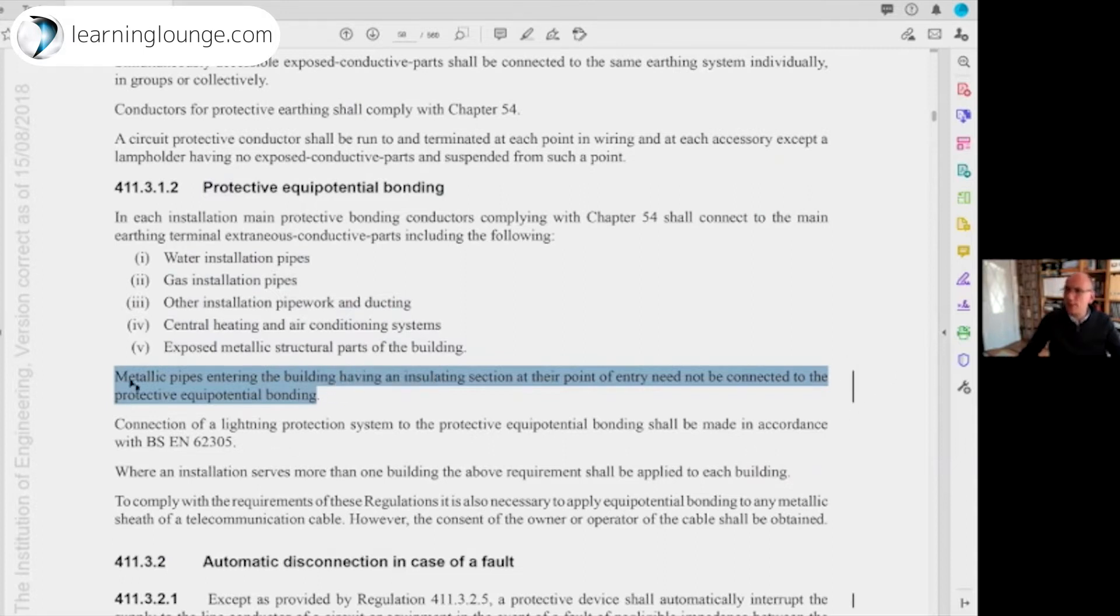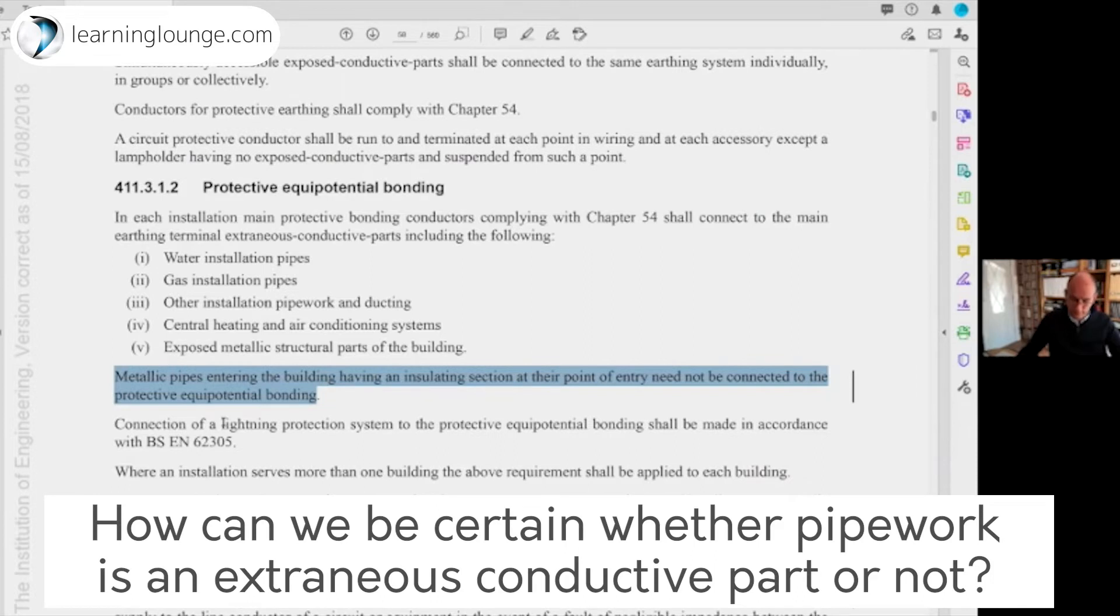What it states is that metallic pipes entering the building having an insulating section at their point of entry need not be connected to the protective bonding. It's not quite as clear as it could be. I think we might see some changes when amendment 2 comes out. Essentially what it means is if you've got plastic pipework coming into the building, you do not need to main bond the gas or the water installation pipes. That really put into words simple, ridiculously simple and clear words, but there are still exceptions aren't there?